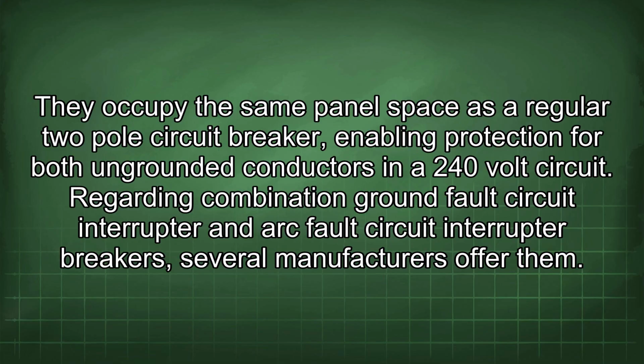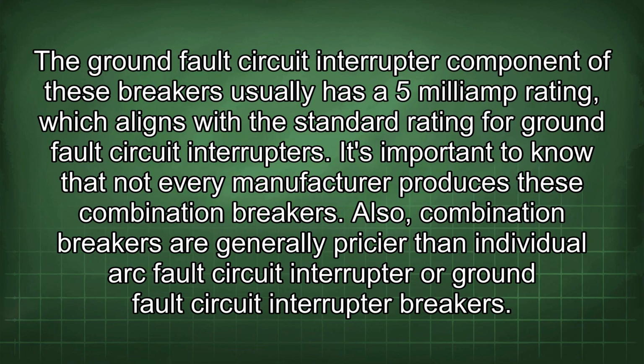Regarding combination ground fault circuit interrupter and arc fault circuit interrupter breakers, several manufacturers offer them. The ground fault circuit interrupter component of these breakers usually has a 5 milliamp rating, which aligns with the standard rating for ground fault circuit interrupters. It's important to know that not every manufacturer produces these combination breakers.